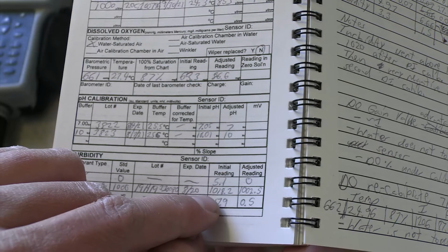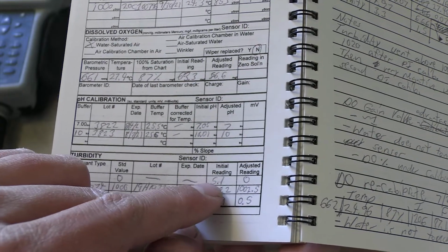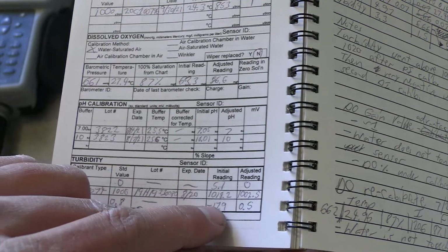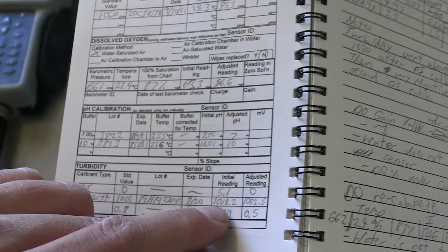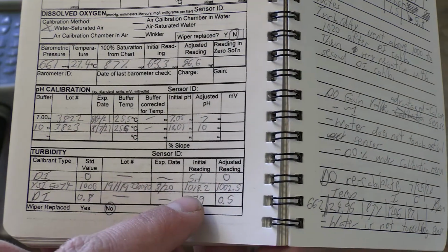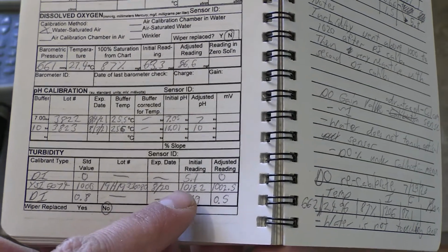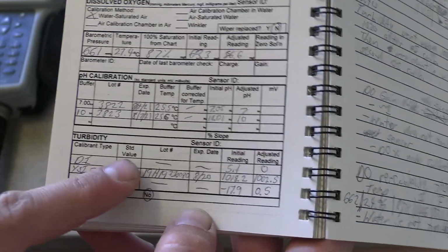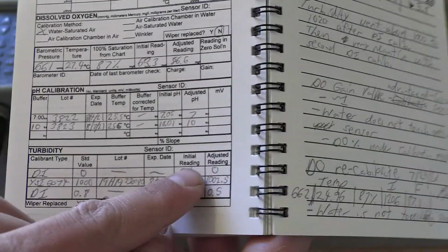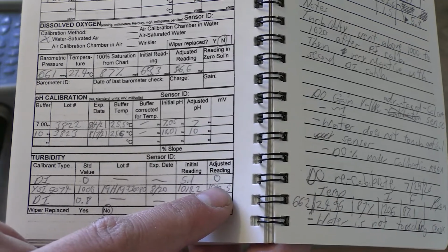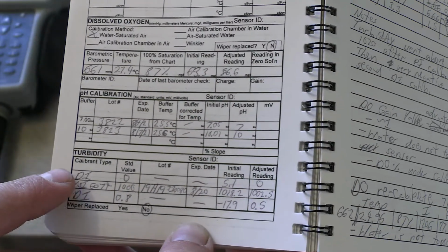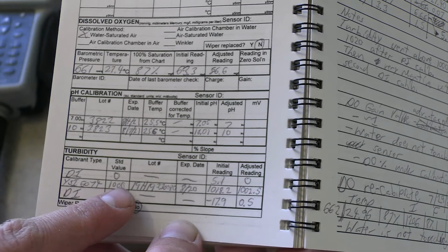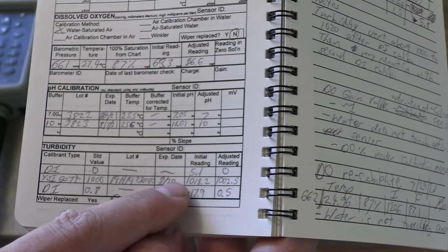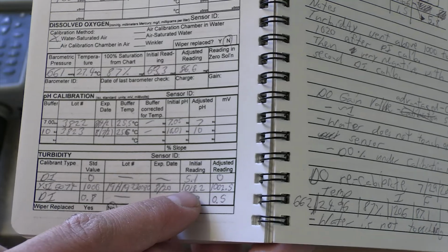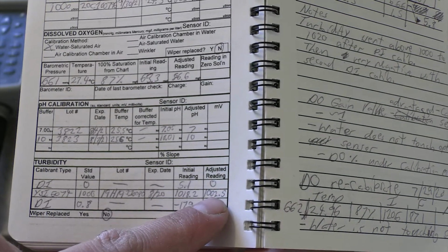And then the initial reading, which is going to be interesting, because sometimes the DI water acts up because it's so pure, and the turbidity sensor is kind of touchy when it comes to really small numbers. So the best way to do this is actually to calibrate DI water first at 0, get a reading and zero it out, and then you go back and do a YSI 6074 at 1,000, and the expiration. Then you get your initial value, and you finalize with it should be about 1,000.